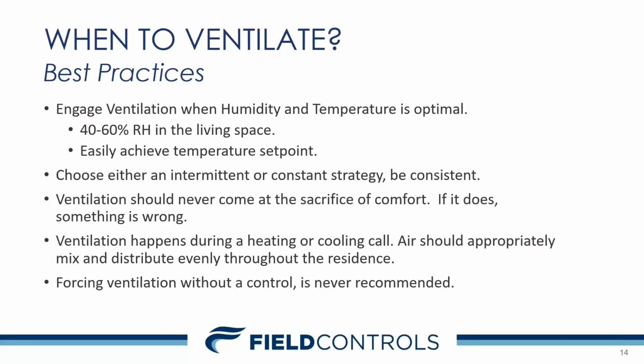Ventilation should never come at the sacrifice of comfort. If it does, something is wrong. Ventilation happens during a heating or cooling call, because then we're not running a subset or a secondary call outside of what is already happening in the home. So any control in the market that you're looking for, whether it's field controls or not, you want to know that that control is going to actively seek to see a heating or cooling call prior to running its own ventilation cycle. Especially in southern climates where you're getting multiple calls an hour, we can divide those calls to mix appropriately with a heating or cooling call to minimize the impact of only bringing in outside air. Air should be appropriately mixed and distributed evenly throughout the residence at that point in time.